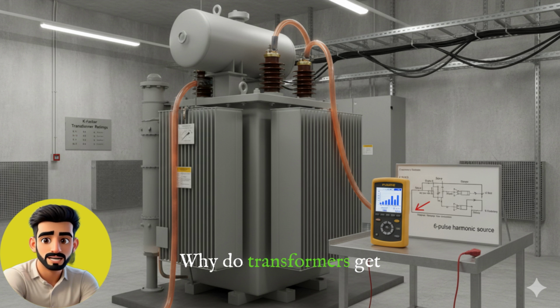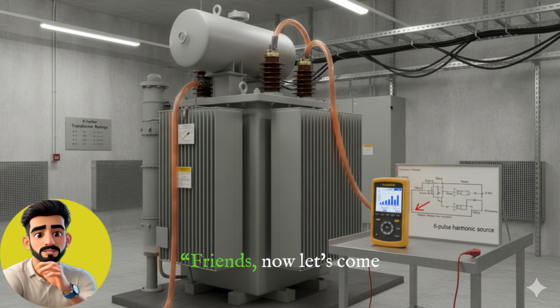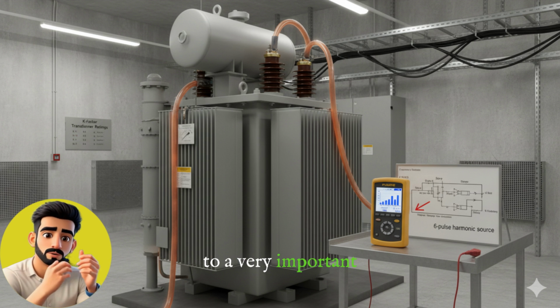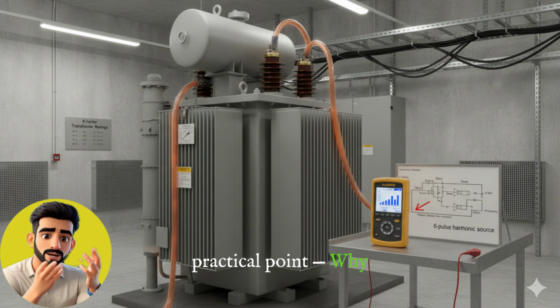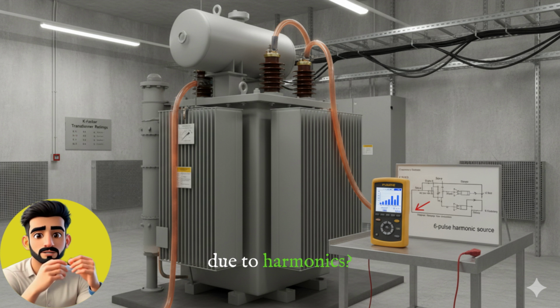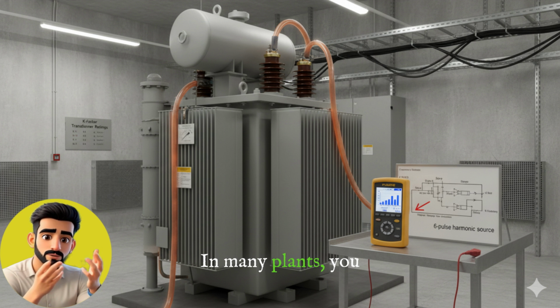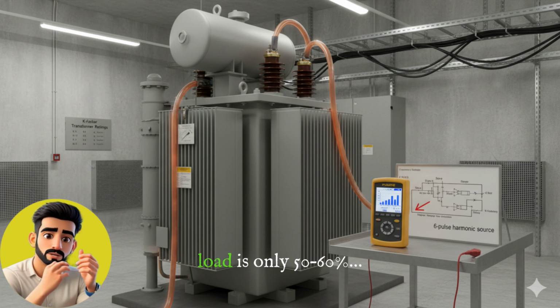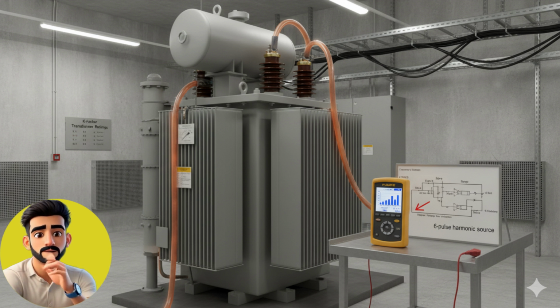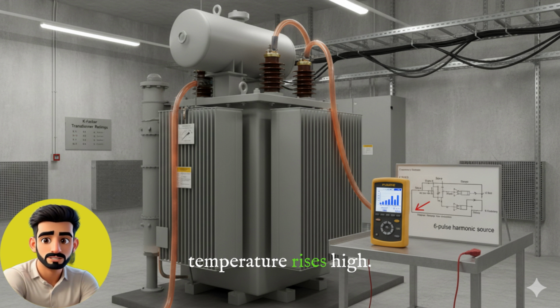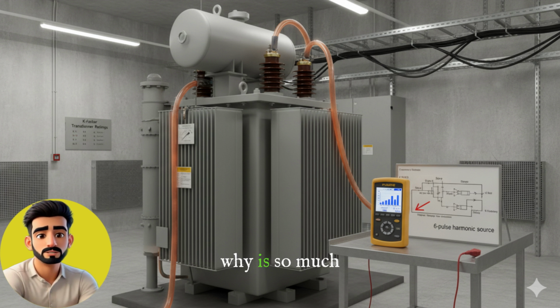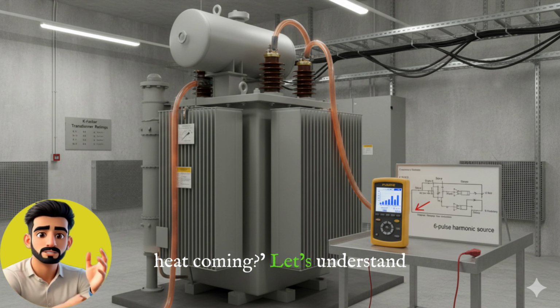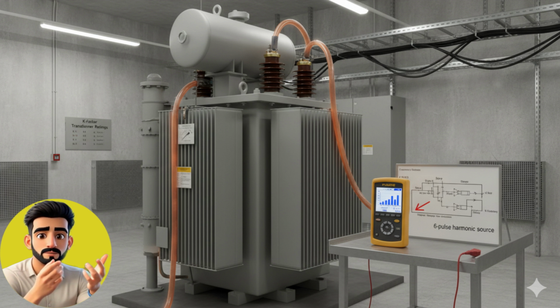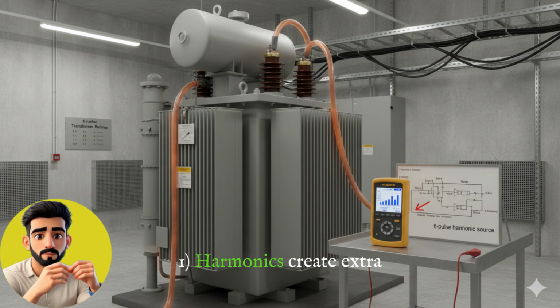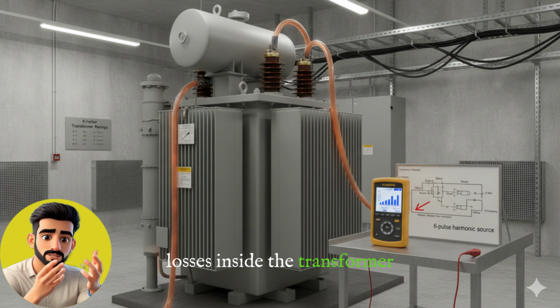Why do transformers get hot? Friends, now let's come to a very important practical point. Why do transformers heat up due to harmonics? In many plants, you might have observed the load is only 50 to 60%, yet the transformer's oil temperature rises high. Engineers think the load is low, then why is so much heat coming? Let's understand this in simple language. 1. Harmonics create extra losses inside the transformer.